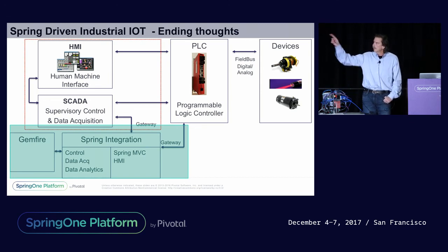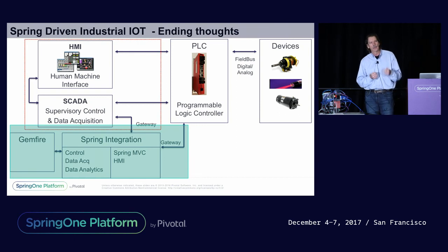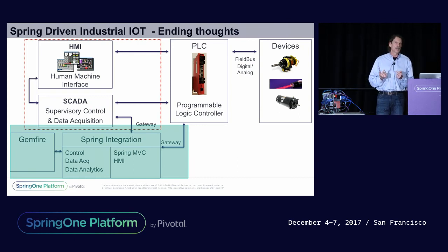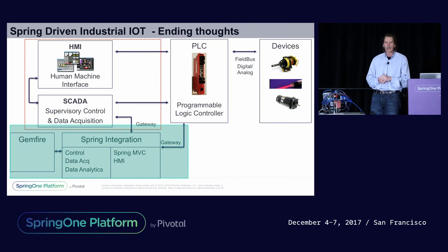In these PLCs, we can wrap the program and we can pass in the control parameters at the beginning of the program and extract data out at the end of the program and never affect the actual program itself. And so this gives us a way to now connect into those low-level controllers that control the physical world without a huge amount of liability.